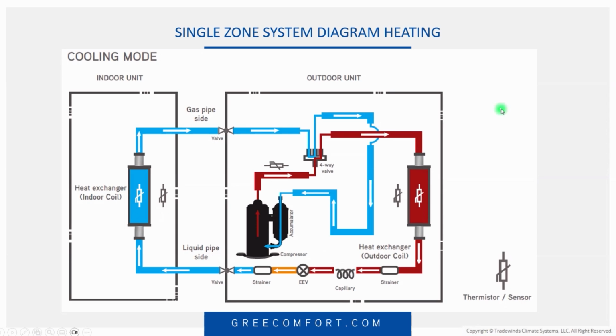Anyway, I want to talk a little bit about the piping to a mini split and the flow of the refrigerant and what the machine's actually doing with all that. So just following our flow here, you're discharging off your compressor, going to your outdoor coil, releasing heat, condensing into a liquid, going through a strainer, capillary tube, EEV, strainer, and then we go into our liquid pipe to feed our indoor evaporator, come back as a gas, go through our reversing valve, back into the compressor and the accumulator, and we start the whole process again.